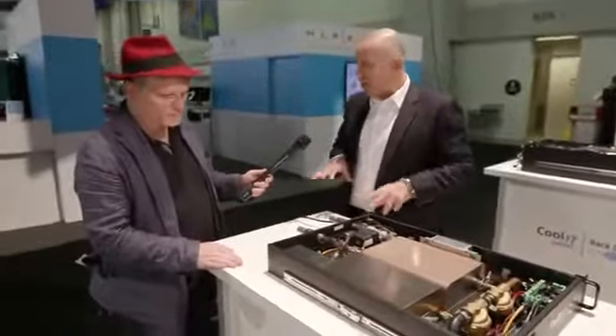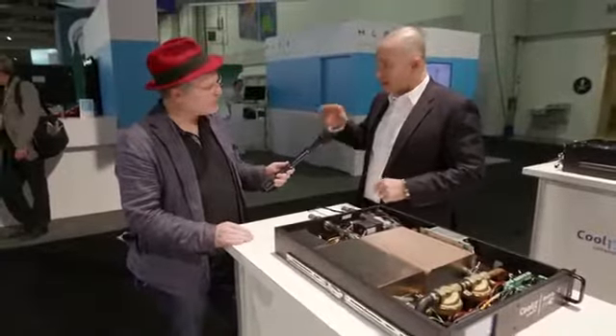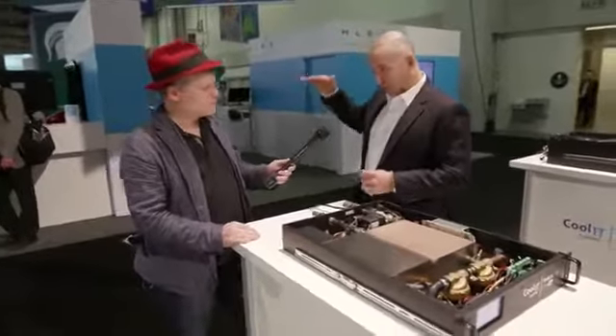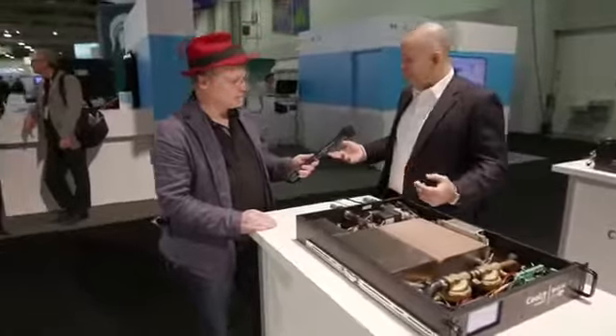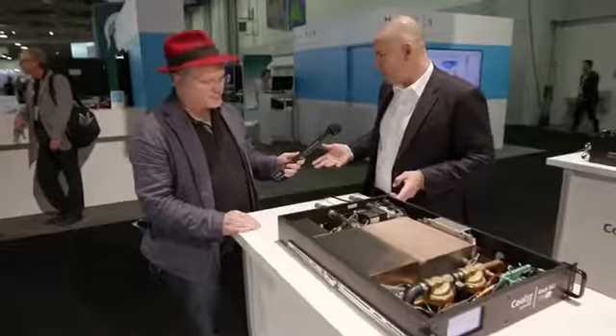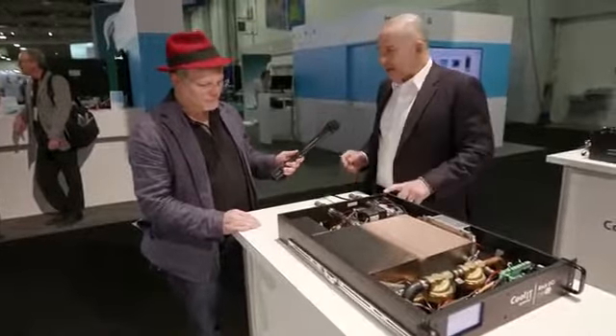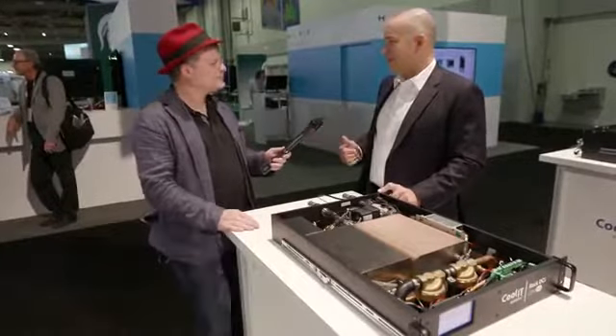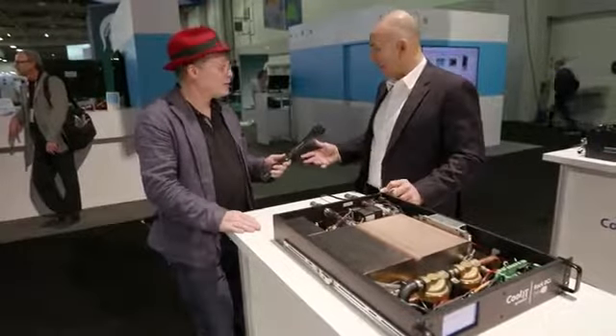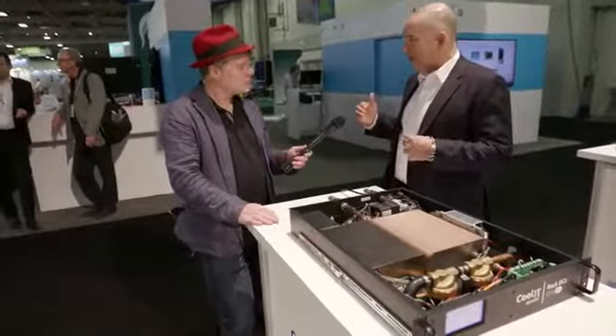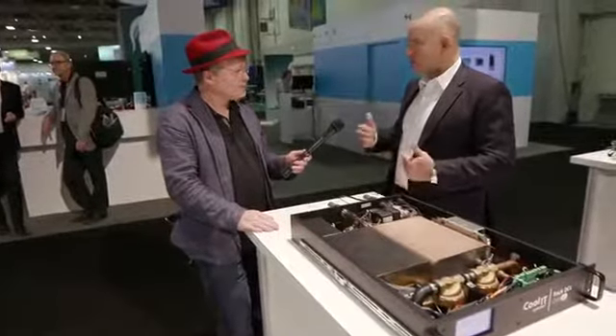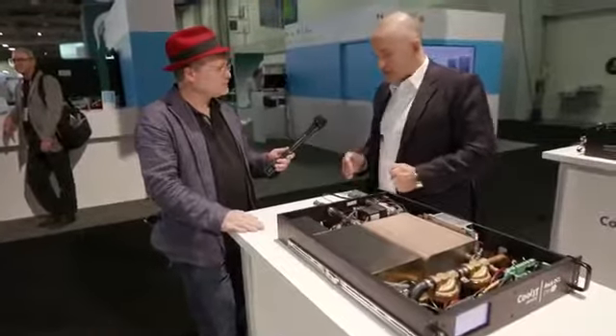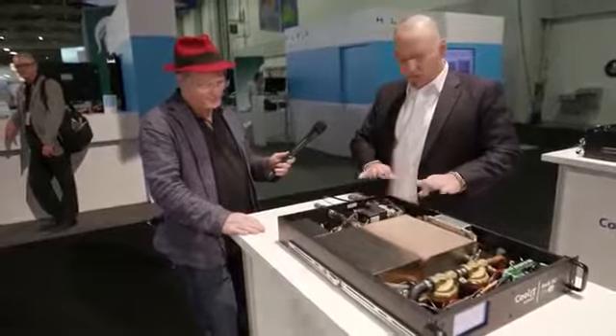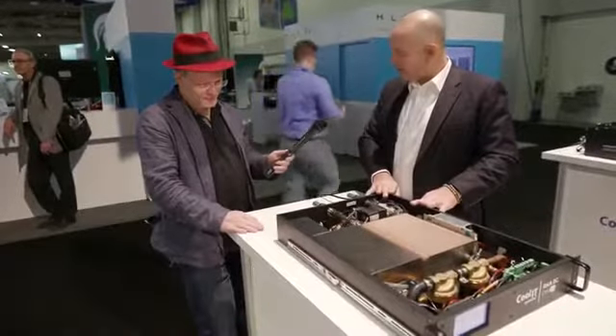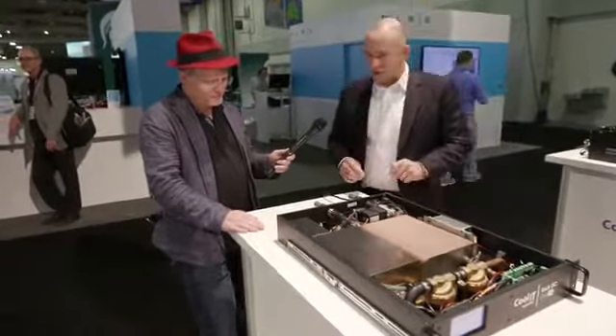So we had about 20 liters a minute, and we try to gauge everything by about half a liter a minute per node. So the quick math suggests we can do about 40 or 42, but now we have racks that are having 100, 120 of those nodes, and even higher heat, like 60, 70, 80 kilowatts. So we decided to move from our standard here, and we're now in production with this.